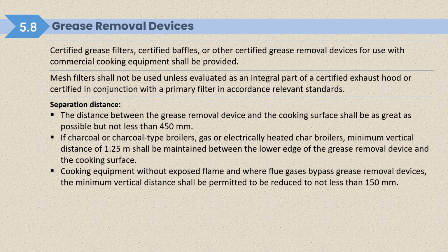Separation distance: the distance between the grease removal device and the cooking surface shall be as great as possible but not less than 450 mm. So this point you should note down. I think this is very important whenever we are installing any cooking appliances. We should make sure the distance between the grease removal device and the cooking surface shall be as great as possible but not less than 450 mm. If charcoal or charcoal type broiler, gas or electrically heated char broiler, a minimum vertical distance of 1.25 meters shall be maintained between the lower edge of the grease removal device and the cooking surface.